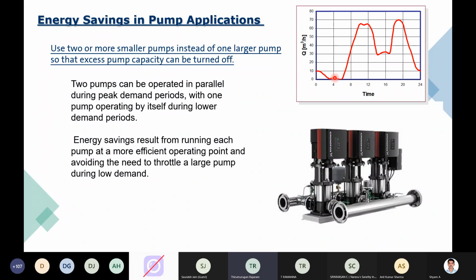So there is no flat scenario of flow consumption. It keeps on varying. So what we can adapt here is to have multiple smaller parallel flow applications. This will help: whenever there's a lean load, one pump can operate, and whenever the load picks up, the second pump also keeps operating. So at any point of time, your pump efficiency would be much higher, and your energy consumption will come down. These kinds of parallel operated kits are being offered.